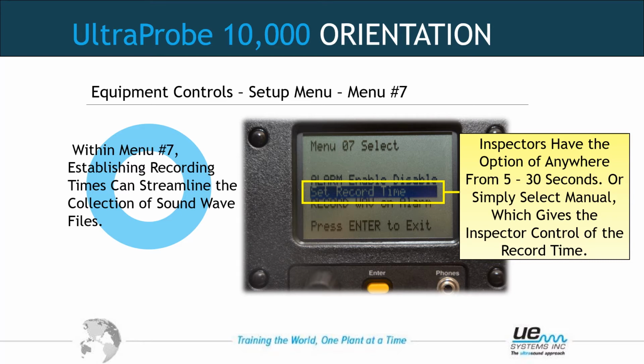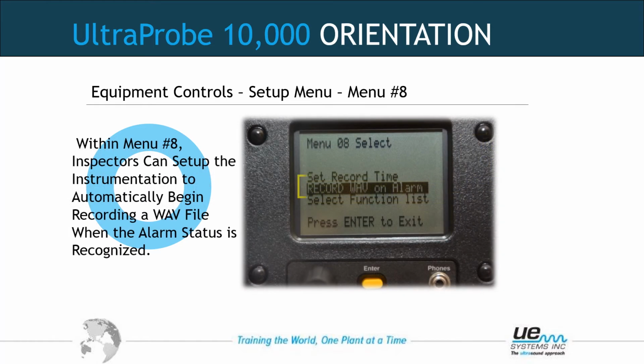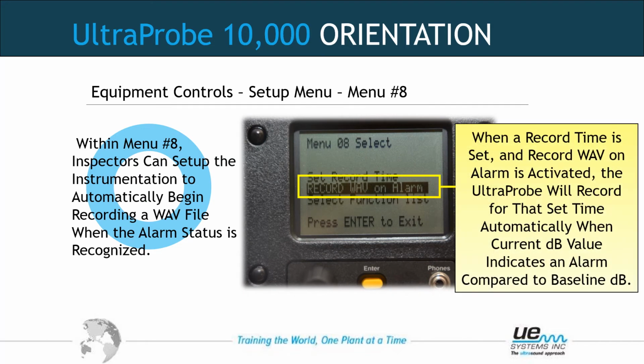Back to the main menu here, menu number 8, record wave on alarm. If you had the alarm value set in the software, the instrument was set up, was in automatic, and as you were trending, you reached one of the alarm values, this will throw you into the recording mode automatically without you having to go to the function bar and choosing record wave time. Do remember, this will not give you a chance to set your sensitivity correctly before recording.